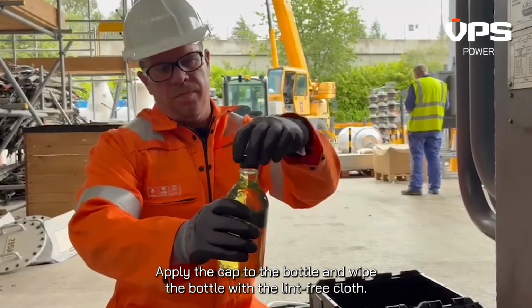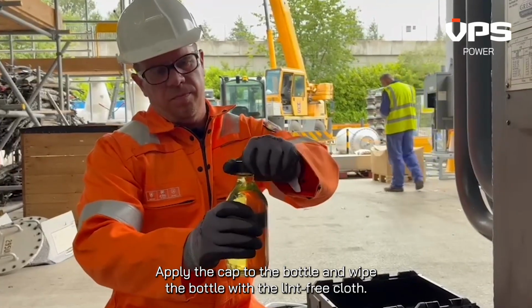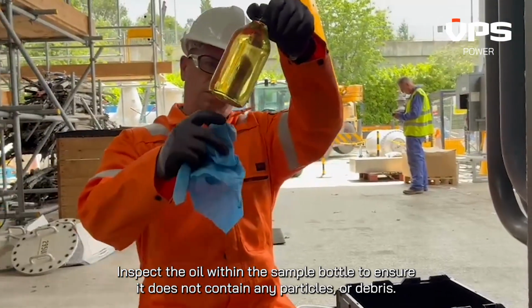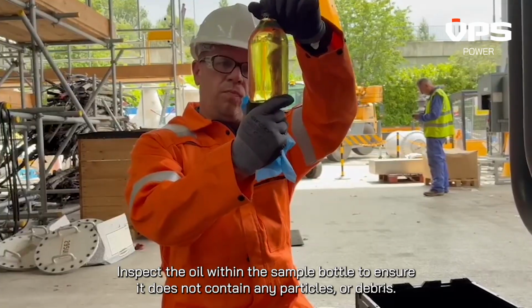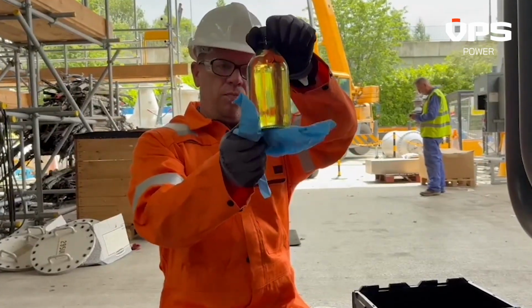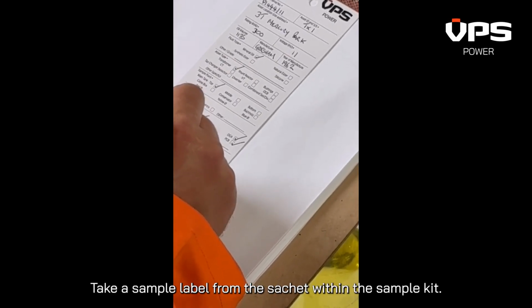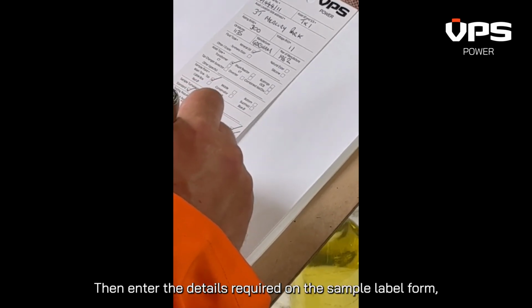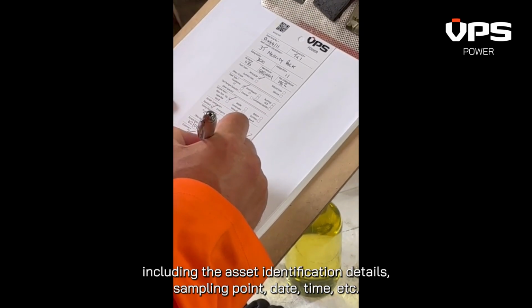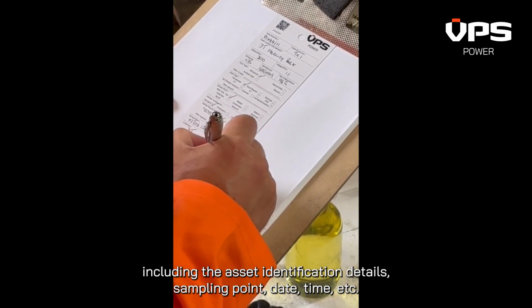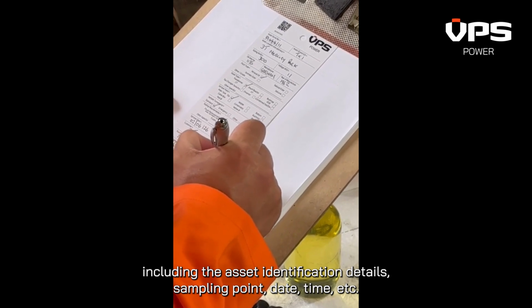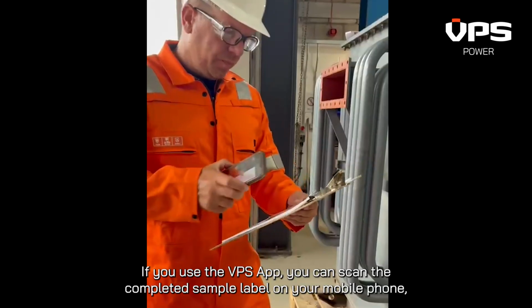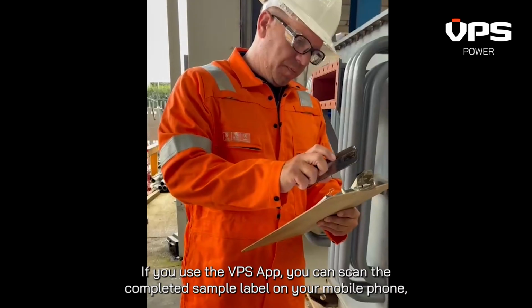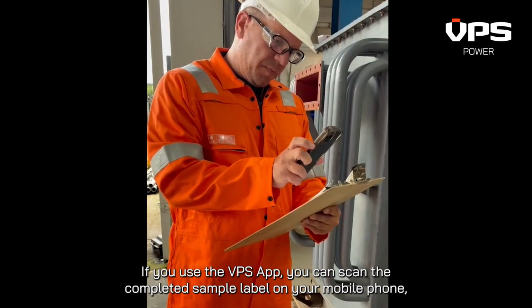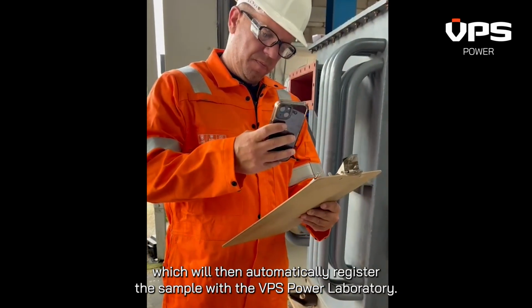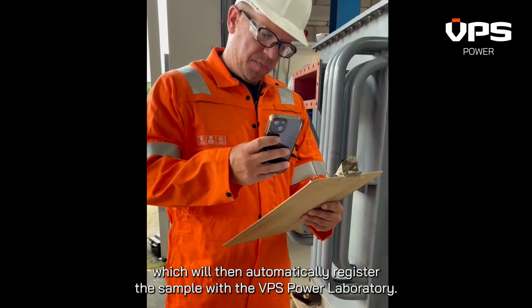Apply the cap to the bottle and wipe the bottle with the lint-free cloth. Inspect the oil within the sample bottle to ensure it does not contain any particles or debris. Take a sample label from the sachet within the sample kit. Then enter the details required on the sample label form, including the asset identification details, sampling point, date, time, etc. If you use the VPS app, you can scan the completed sample label on your mobile phone, which will then automatically register the sample with the VPS Power laboratory.